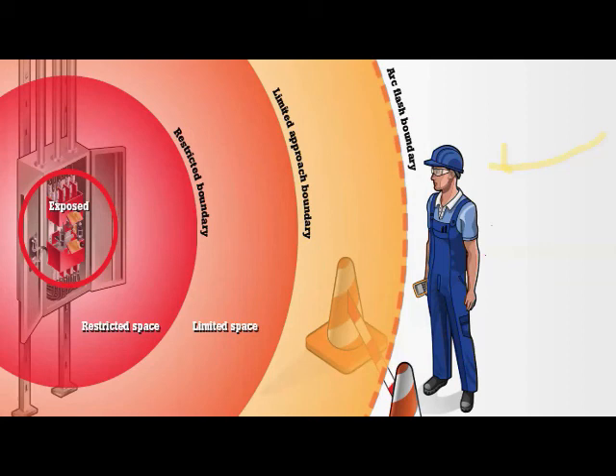It is normally approximately 1 meter up to 600 volts, but a person can't do all the work standing far away at that distance. If you want to enter further inside, you go to another boundary called the limited approach boundary. If a person wants to work in the orange colored space, that is the first boundary area, and he should be an electrical person, or unqualified but wearing basic PPE. If a person wants to work in the semi-red colored area, that is called the limited approach boundary, and he must be a qualified person.